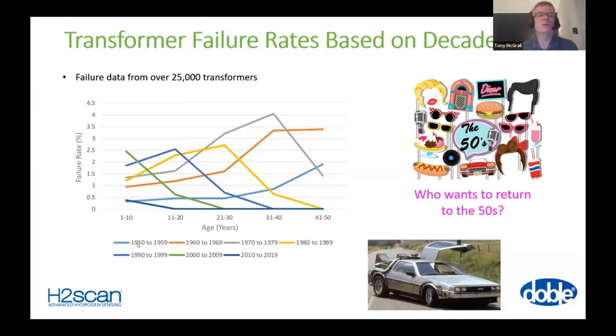And so there's a light blue line towards the bottom of the chart. And you can see for those, there isn't much of an infant mortality, but over decades, there is a rise in that failure rate, and it's still rising when you get to 40 plus years old. So for the next decade in orange, a little bit further up, we can see the transformers from 1960 to 69 vintage. And we can see that in the first 10 years, there is a failure rate of about 1%. Then that rises so that in the next 10 years, it's higher and then rises again, as if that blue line has been moved to the left.